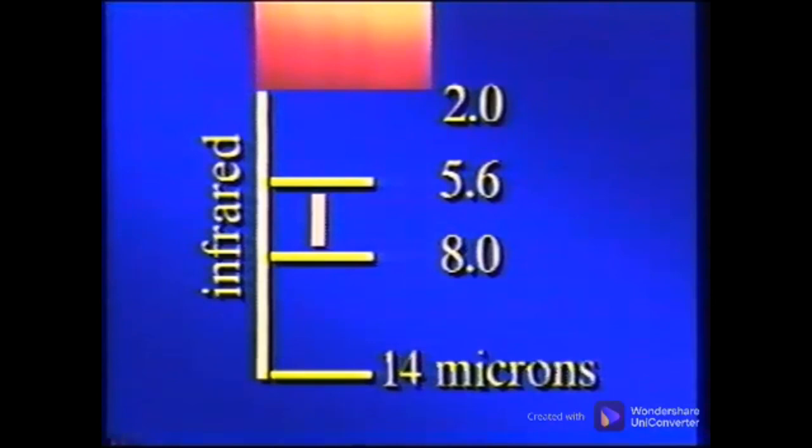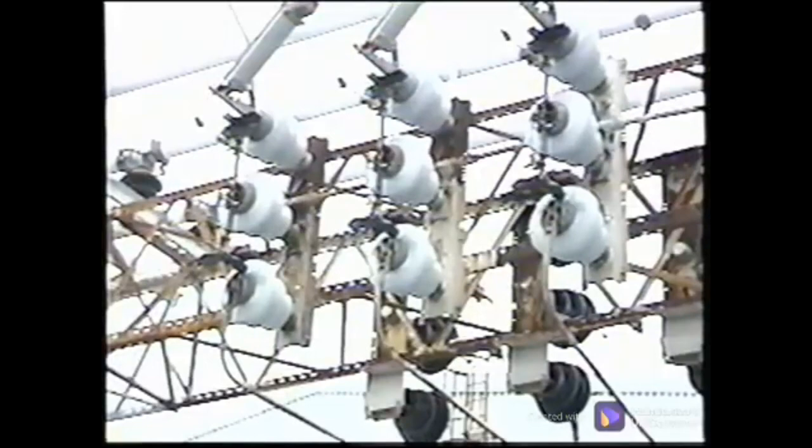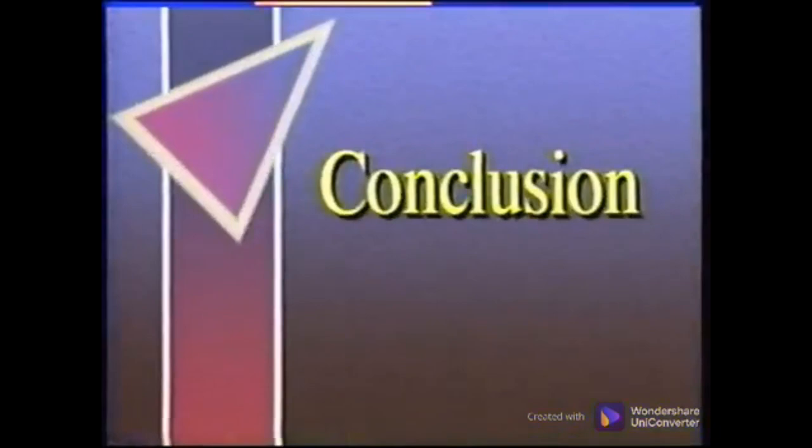The camera that is sensitive to the shortwave region is better for high temperatures and is not as susceptible to night sky reflections. This means it would be best for surveying roofs of buildings and any high temperature processes that use refractory ovens or hot chemical processes. The long-wave cameras are best for ambient temperatures and less sensitive to solar reflection. They would be best for performing daytime scans of switchyards or electrical applications that are not subject to extreme heat. Use the wavelength that is best for your application.